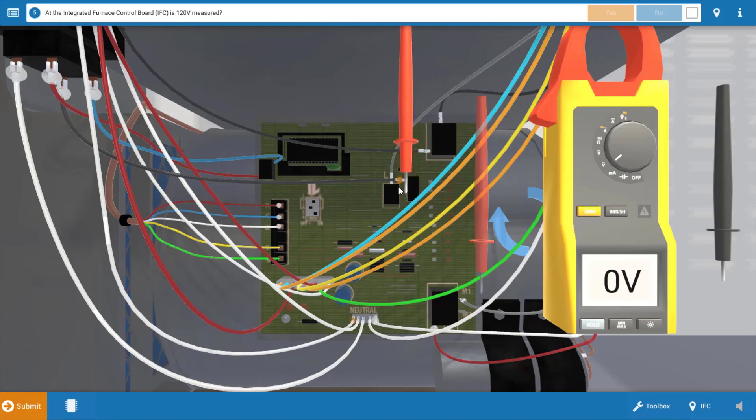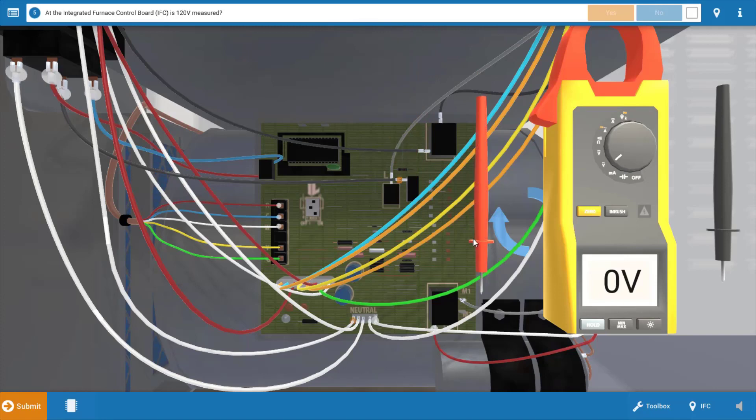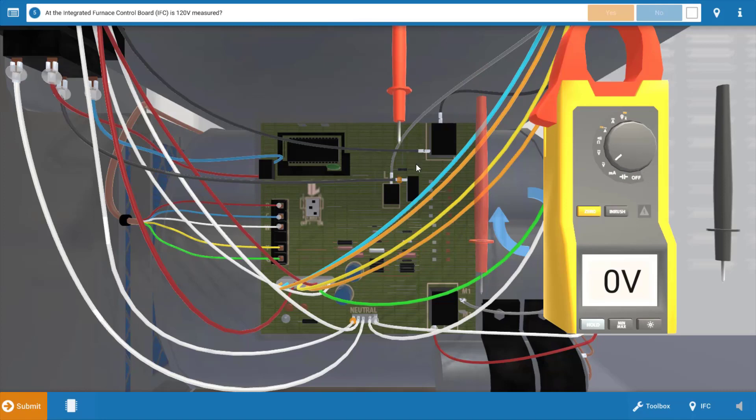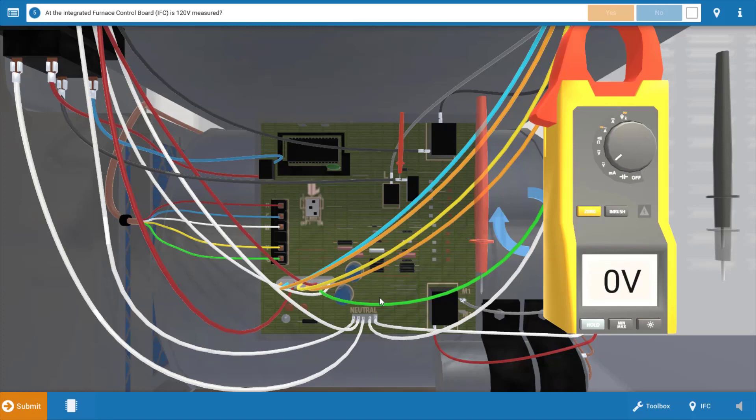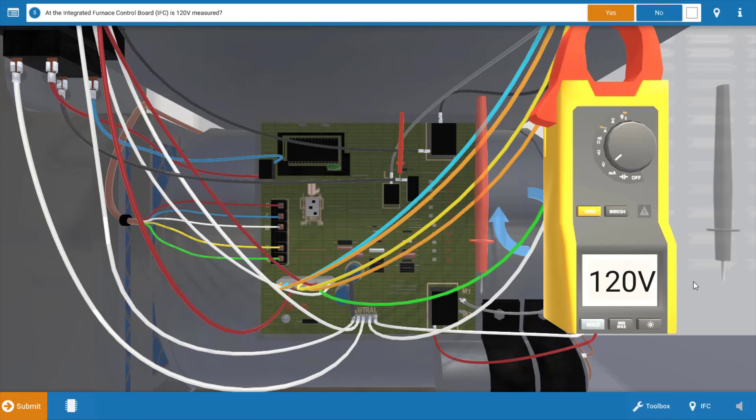The line connection is right here at this glowing orange hotspot and we can just drop one of our leads right on there. Our other lead can be placed at the neutral connection or the neutral block at the bottom of the IFC, right on that glowing orange hotspot. We see we have 120 volts and this verifies that we do have power being received at the IFC. So we're going to click yes on the procedure guide.